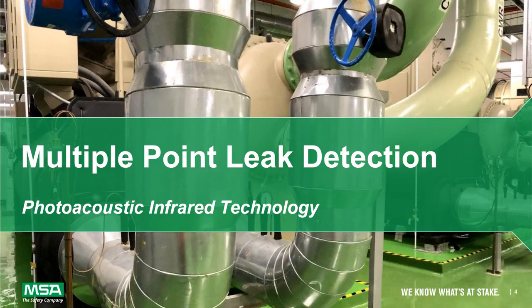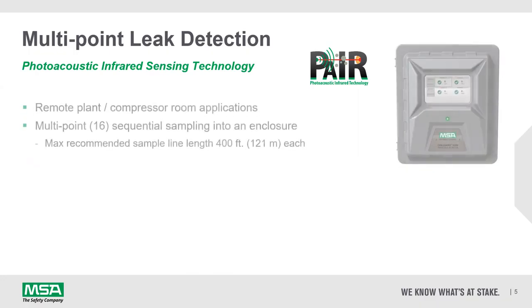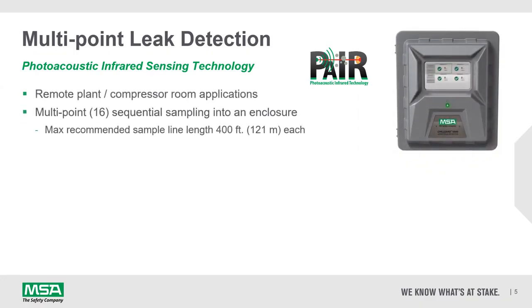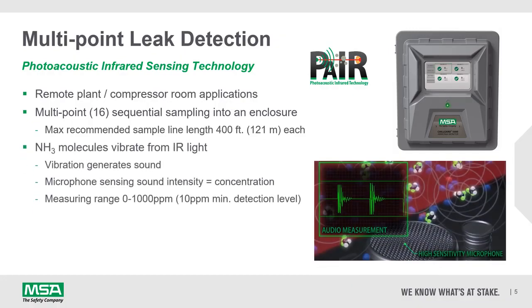First, let's have a look at multi-point leak detection using photoacoustic infrared technology. These multi-point detection systems are typically used in remote plant compressor room applications. They consist of a multi-point sequential sampling system pulling samples of atmosphere to an enclosure over distances of over 120 meters. Inside the enclosure, the sensing technology works on the principle that the ammonia molecules will vibrate in the presence of a specific wavelength of IR light.